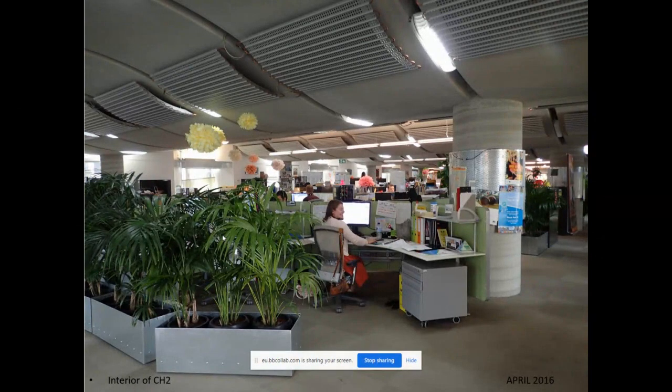Normally a plant in an office has to be taken away every 3 months and replaced. This didn't happen in our office. That was the sort of canary in the coal mine test for good air conditioning. The air conditioning system I've described was extremely popular. That was the most successful thing about this building, the displacement ventilation. People who suffer from dry air and recirculated air were very happy with the displacement system.